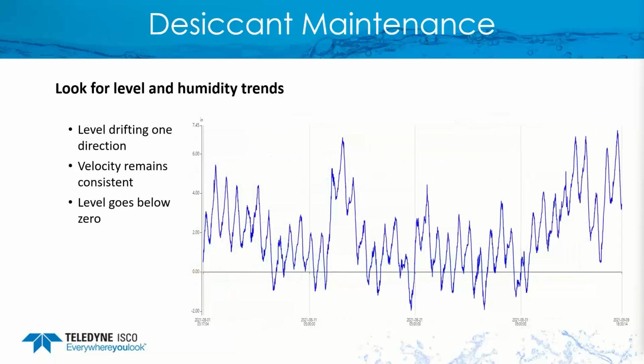So an example here, as far as with the level drifting, if your desiccant was plugged, either from debris, moisture, excessive moisture, what you'll find is that your level may actually go above and below zero. And what happens there is that pressure transducers usually have a referenced atmosphere, which goes through that desiccant tube. And if it no longer references atmosphere, as the barometric pressure changes, you will actually see your level going above and potentially below zero.